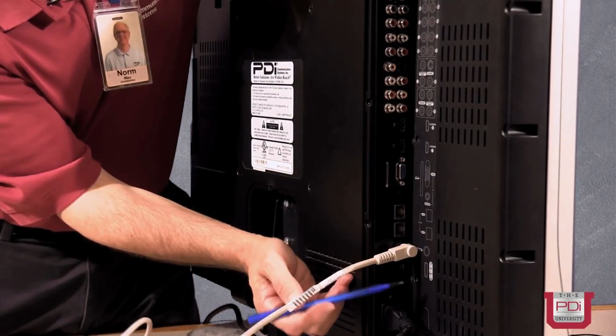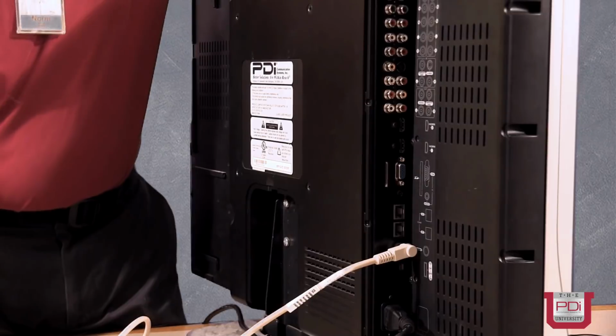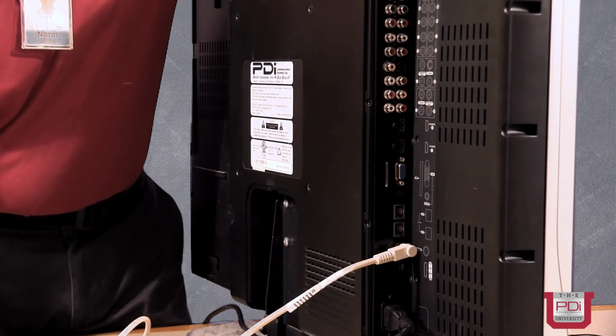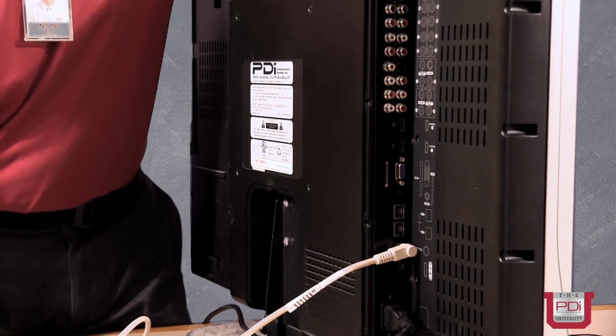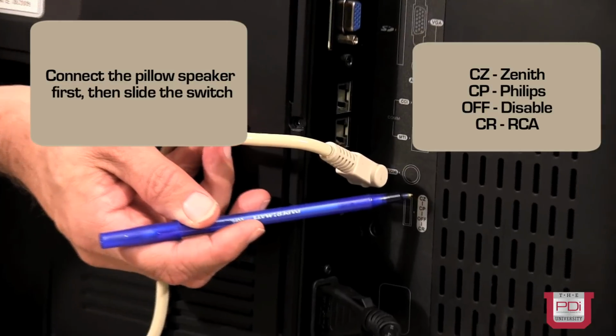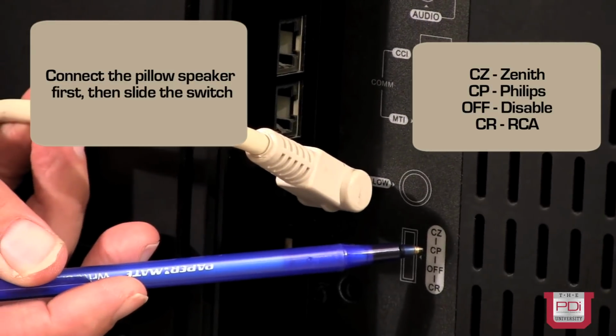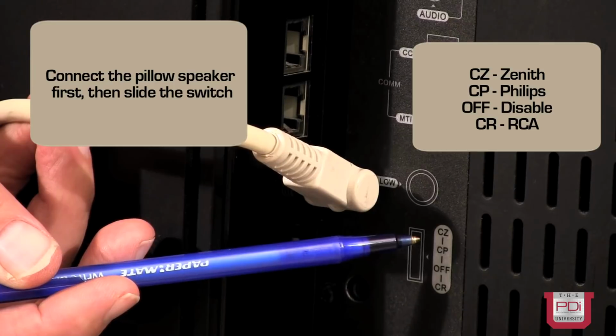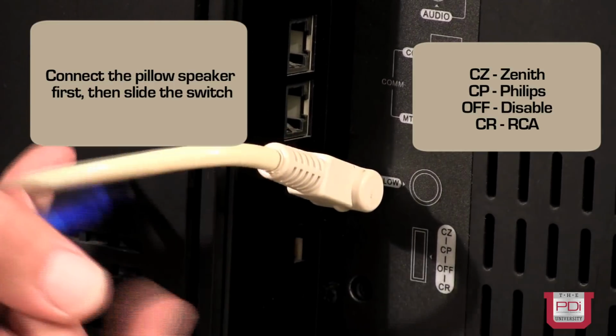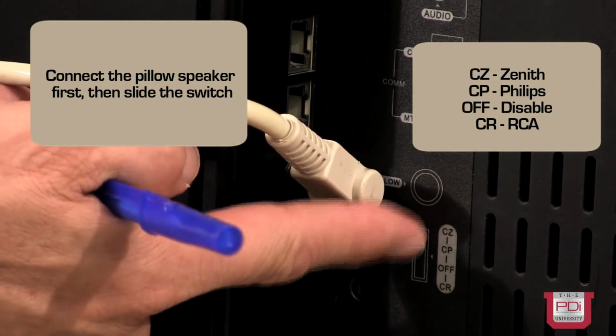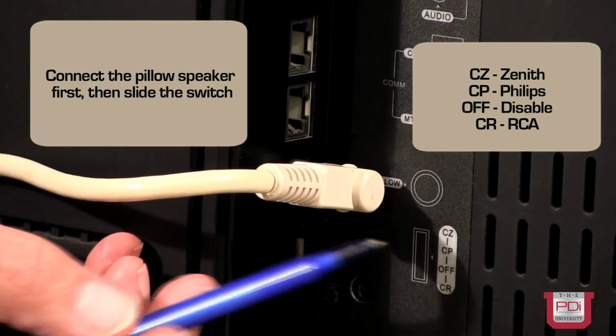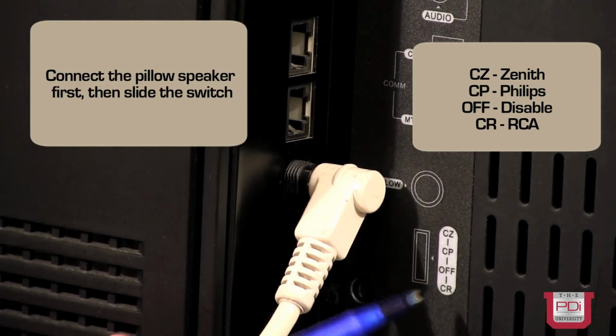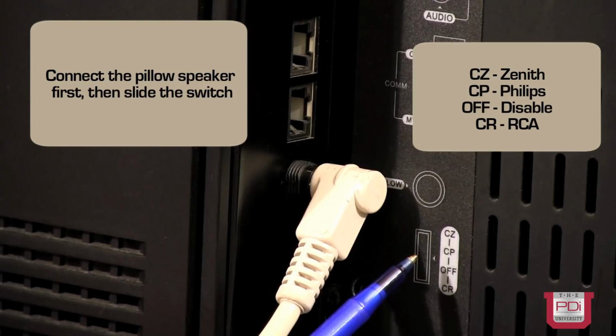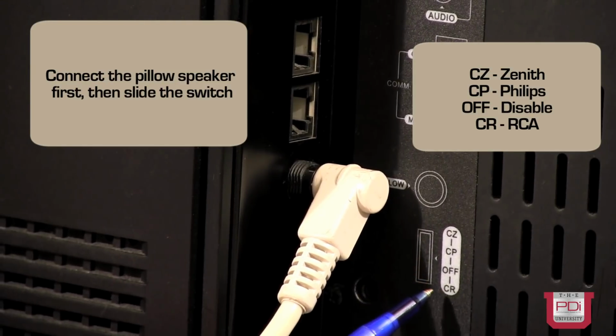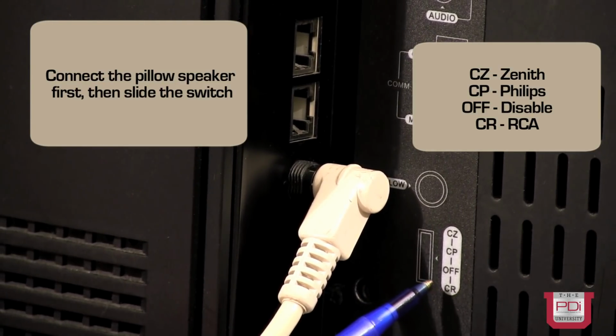And this slide switch allows you to set the compatibility of the TV to recognize a certain style of pillow speaker. We have CZ, which stands for Zenith. So if you had a Zenith compatible pillow speaker, you would slide the switch up to the CZ position. CP, which stands for Philips. There's an off position, which disables the pillow speaker, and a CR position for RCA.